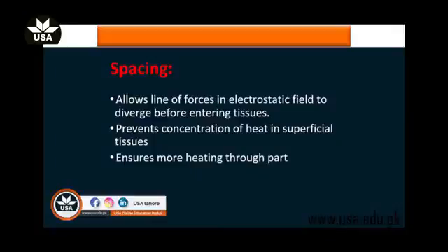The first factor we have is spacing. Firstly, let me explain the significance of spacing. Spacing allows the lines of force and electrostatic field to diverge before entering the tissues, and thus prevents the concentration of heat in superficial tissues, in order to ensure more heating throughout the part.